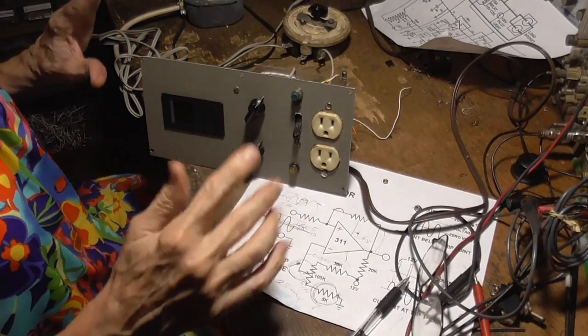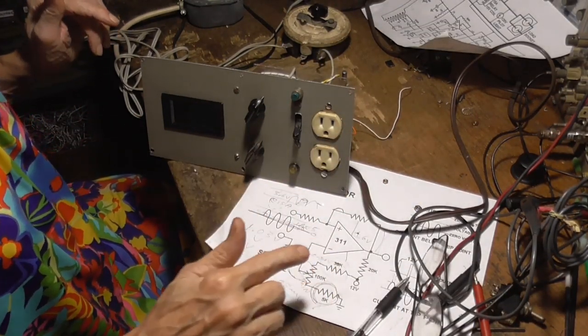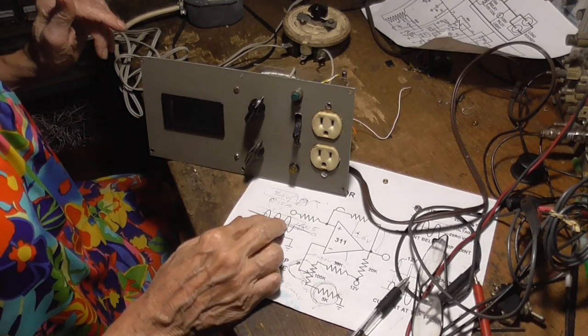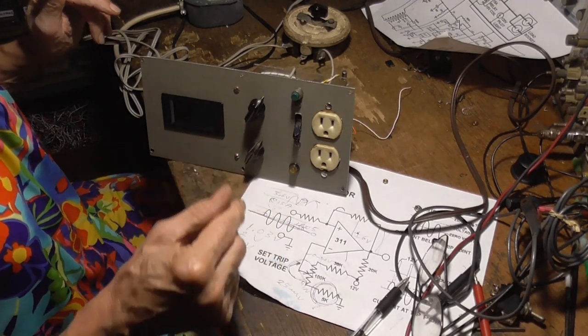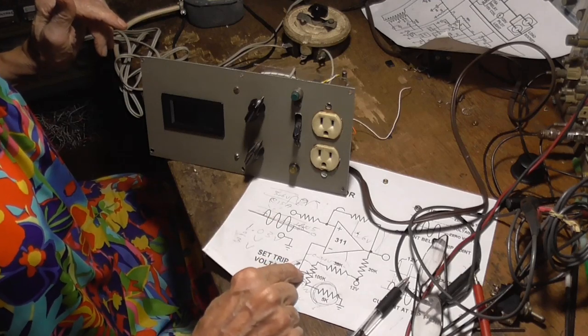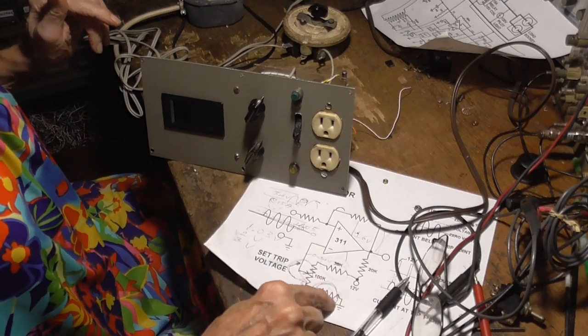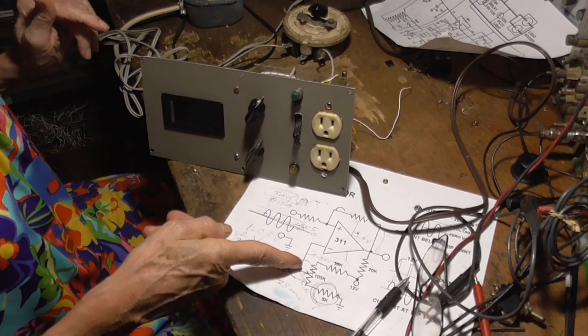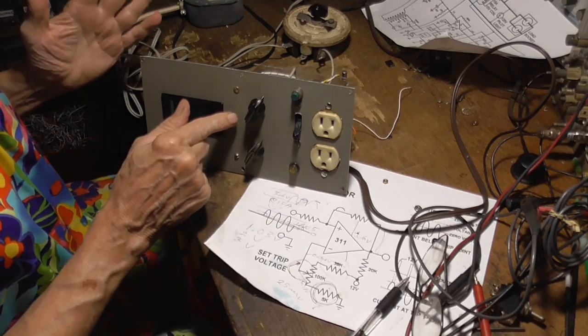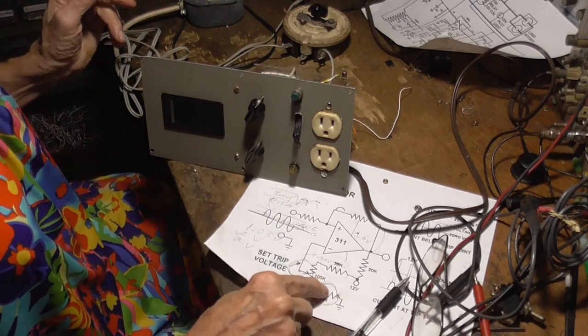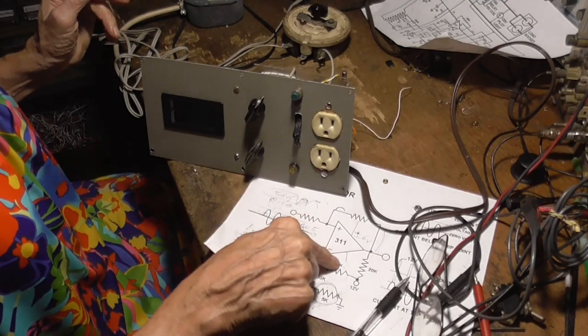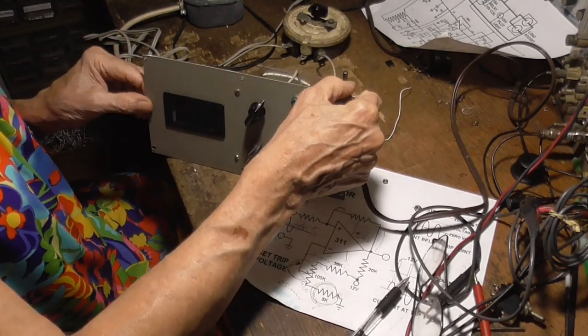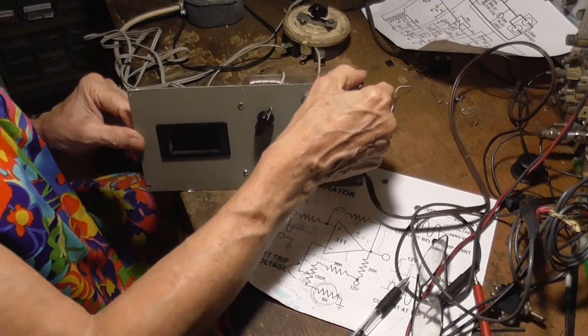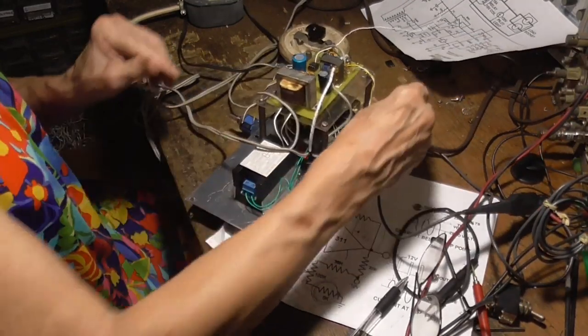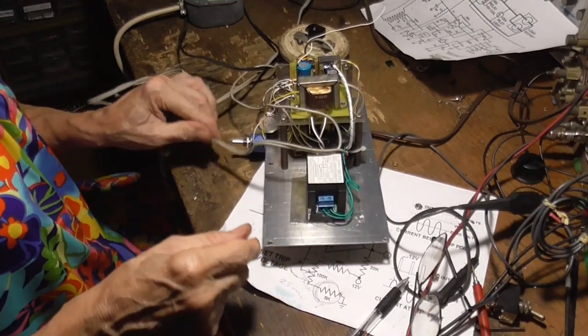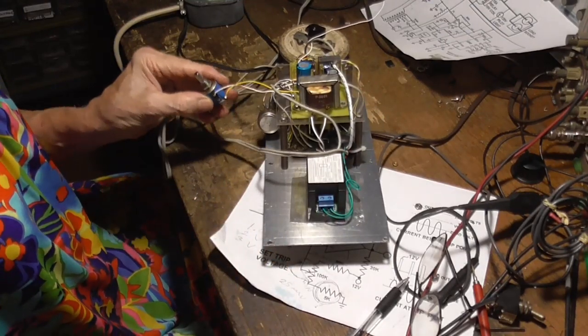So that's how you go ahead and set these two resistors: you measure your peak voltage at 5 amps, and then set this voltage using these resistors to where at 5 amps you have the right voltage. Then go down to 0 or 1 amp, whatever you want your minimum to be, and set this one. Go to 15 amps and set this one. It should be a fairly linear change. All right, let's go ahead and see what these resistors are.